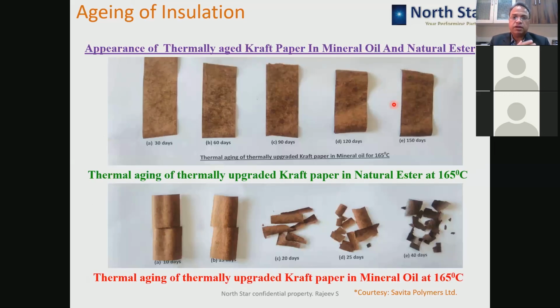Okay, so let us have a look at how the insulation aging happens in mineral oil and in ester oils. It is a laboratory test. It is an accelerated aging test where samples of the insulation impregnated in the liquid insulation are put at a temperature of 165 degrees centigrade. This image is with ester. If you look at the 30th day and 150th day, the condition of the insulation is not much changed. It is still intact, still in shape, and the color is also maintained.